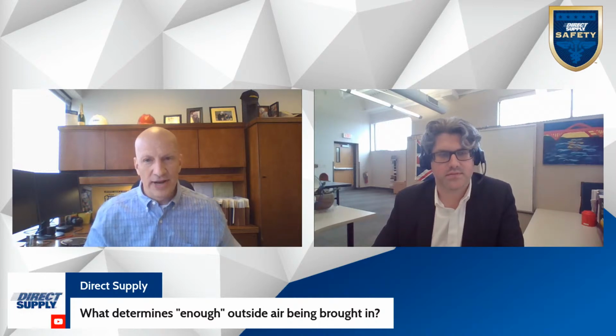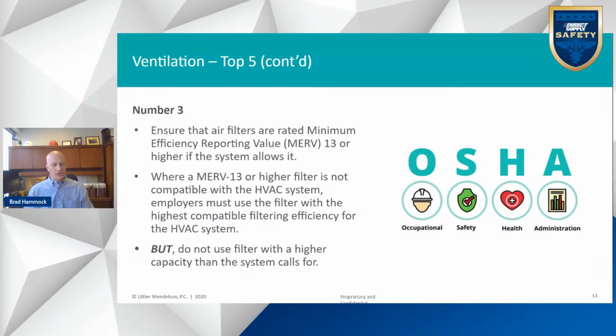Okay, number three of the top five. Of course, there's never a ventilation requirement without something related to air filters. OSHA has requirements here: you need to ensure air filters are rated with a Minimum Efficiency Reporting Value, MERV, of 13 or higher if your system allows it. If your system does not allow such a filter, then you must use the filter with the highest compatible filtering efficiency for the HVAC system.